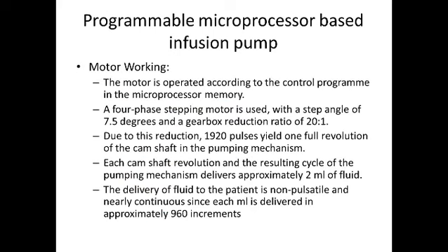Now, how the motor is actually working there. So these are some technical aspects about the infusion pump. The motor is operated according to the control program in the microprocessor memory. A 4-phase stepping motor is used with a step angle of 7.5 degrees. So this is a 4-phase stepping motor with step angle of 7.5 degrees and gearbox reduction of 20:1.